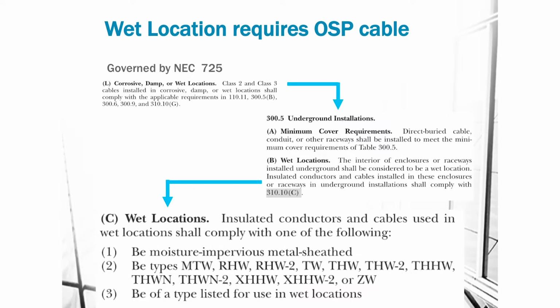And the way that, again, I'm reading the code, there's some code hopping involved, but because we're in 725, that refers to a section in 300 and then 310 that says, okay, if you're routing a cable in a wet location, then it needs to meet one of these 3 requirements. Moisture impervious metal sheathed, and then these are all electrical power conductor types, and then the bottom is it can be listed for use in wet locations. So that's where I'm at with it.